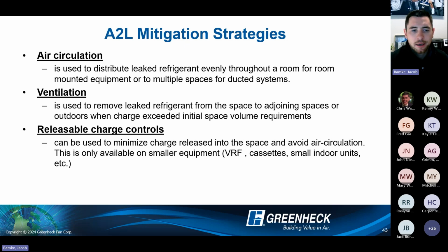And then the last one is what we call releasable charge controls. This can be used to minimize the actual charge that's released into the space, and you could actually avoid the need for air circulation. So it's only available on smaller equipment: VRF, cassettes, small indoor units. Basically what that's saying is, if there's a leak at the condensing unit or something upstream of this equipment, we have a shutoff valve or something that keeps that refrigerant from getting into the space itself. When we do that, we might not have to turn that air circulation on. So those are a few mitigation strategies that will make more sense as we get into either today or future training that we might host.